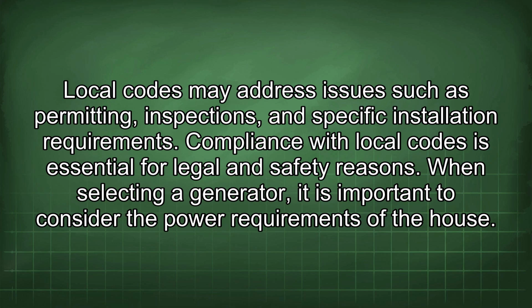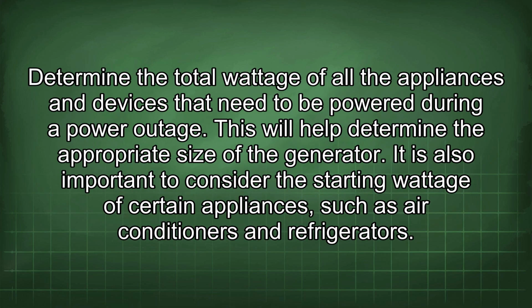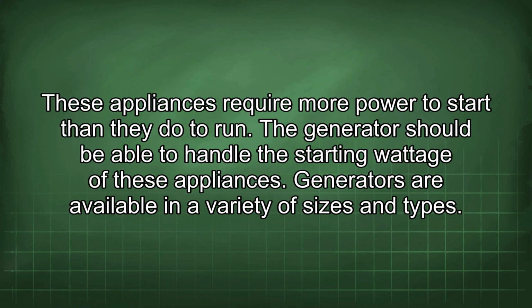When selecting a generator, it is important to consider the power requirements of the house. Determine the total wattage of all the appliances and devices that need to be powered during a power outage. This will help determine the appropriate size of the generator. It is also important to consider the starting wattage of certain appliances, such as air conditioners and refrigerators. These appliances require more power to start than they do to run. The generator should be able to handle the starting wattage of these appliances.